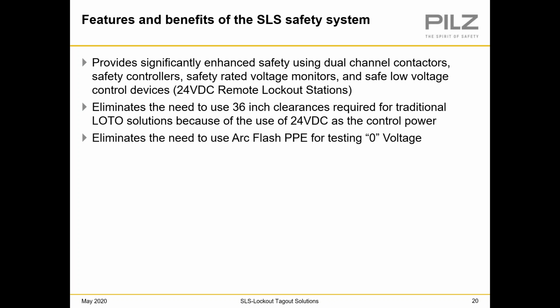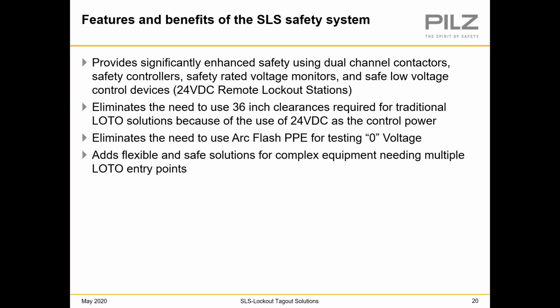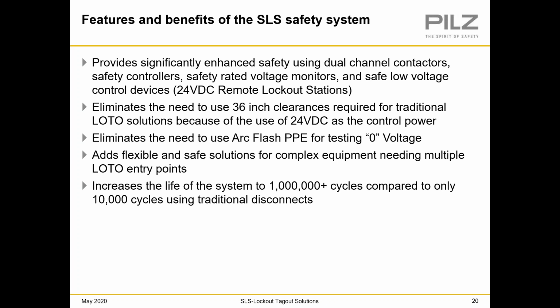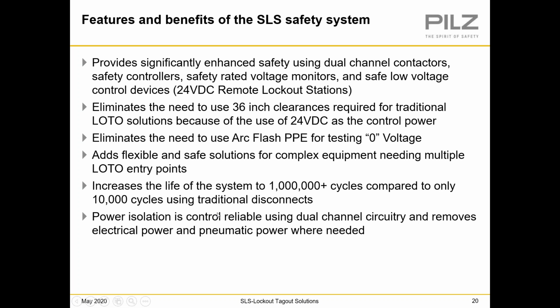It eliminates the need to use arc flash equipment when testing for zero voltage, because there's potential for arc flash when you're using traditional lockout procedures using a disconnect. It adds flexible and safe solutions for complex equipment needing multiple lockout entry points. It increases the life of the system to 1 million+ cycles compared to only 10,000 cycles when you're using traditional disconnects as a lockout device.